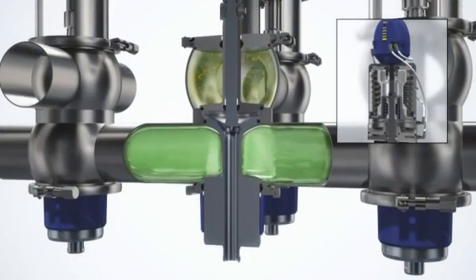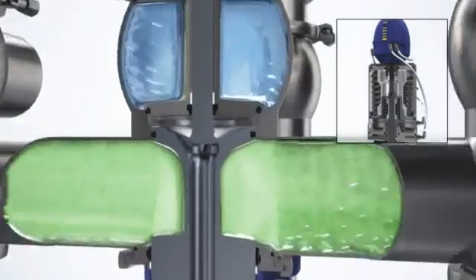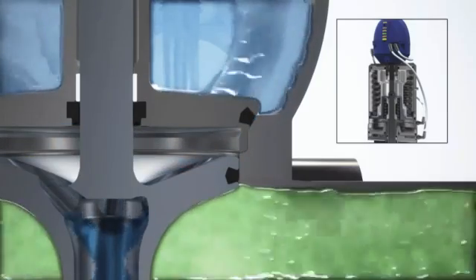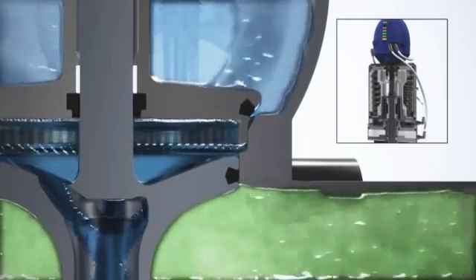It is completely safe to clean the upper valve body and the upper plug seal of an Alfa Laval unique mix-proof valve while product is flowing through the lower section of the valve body. The fast-acting seat lift for cleaning the upper plug seal always creates a throttling edge due to the defined metal-to-metal stop in the actuator.